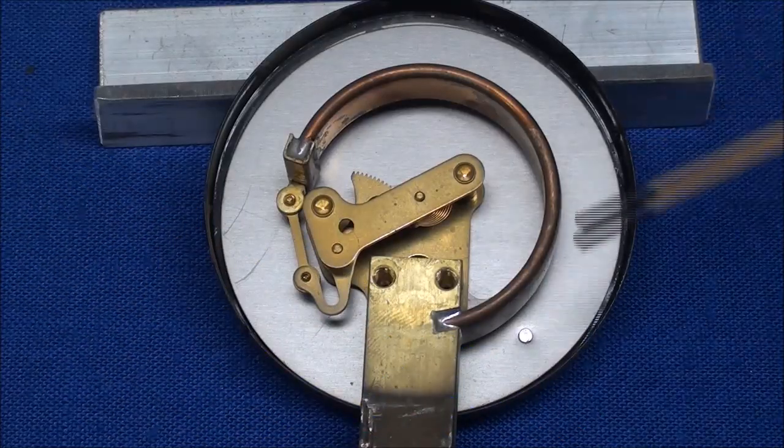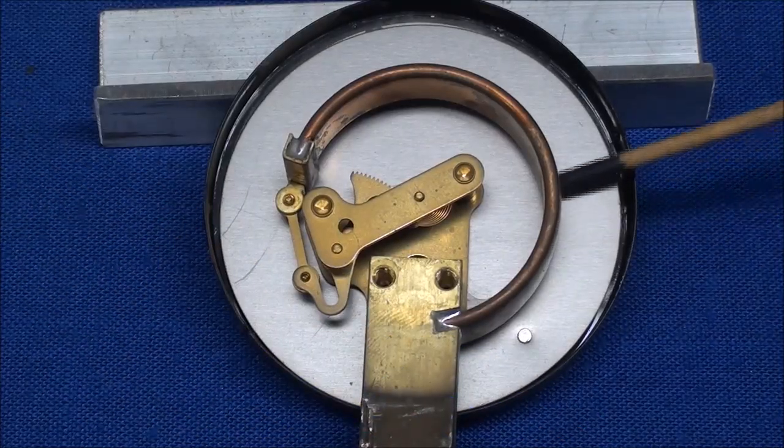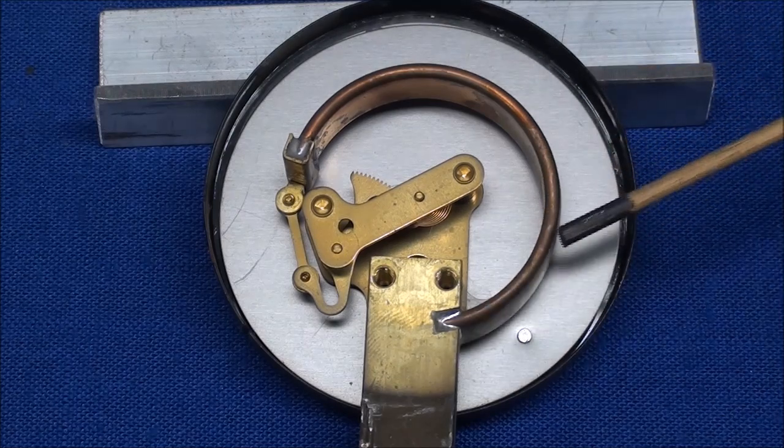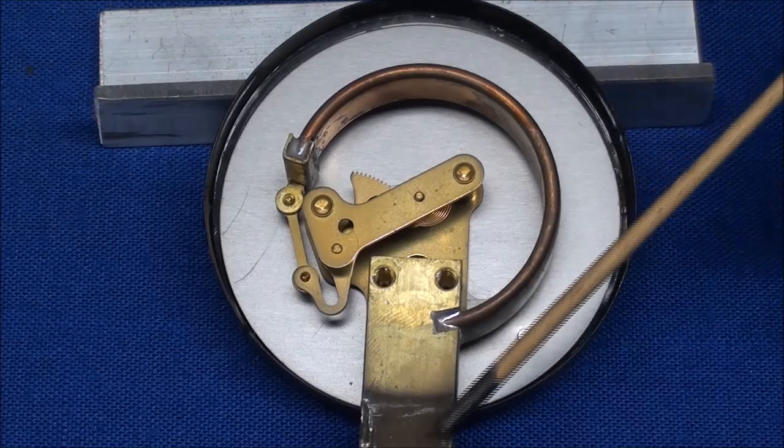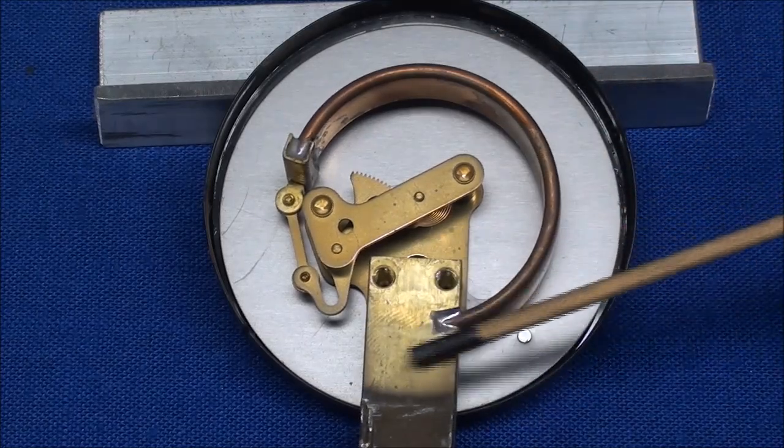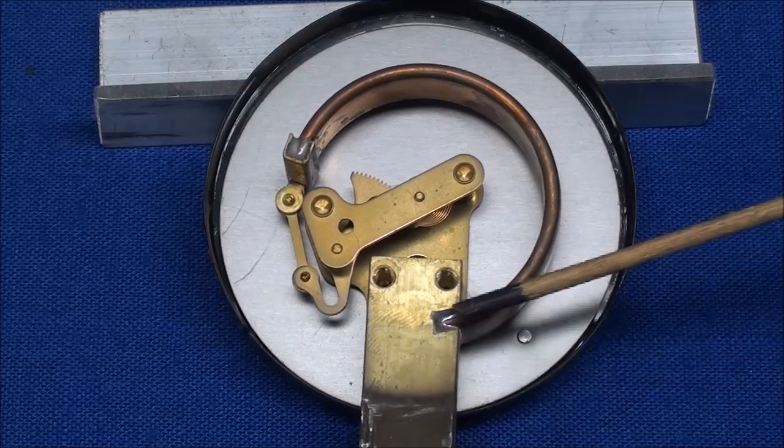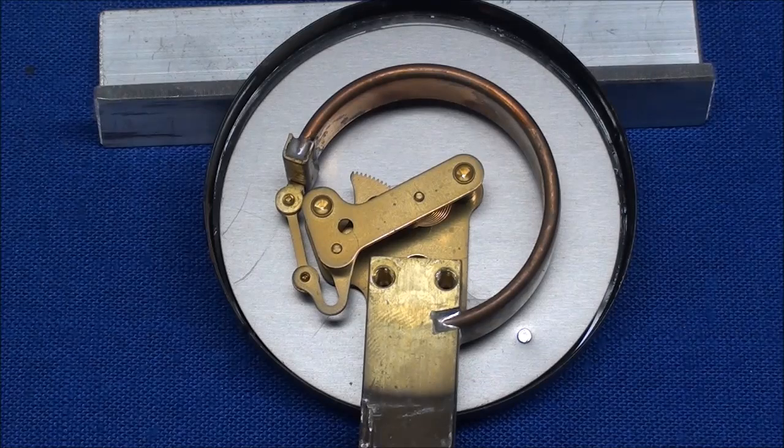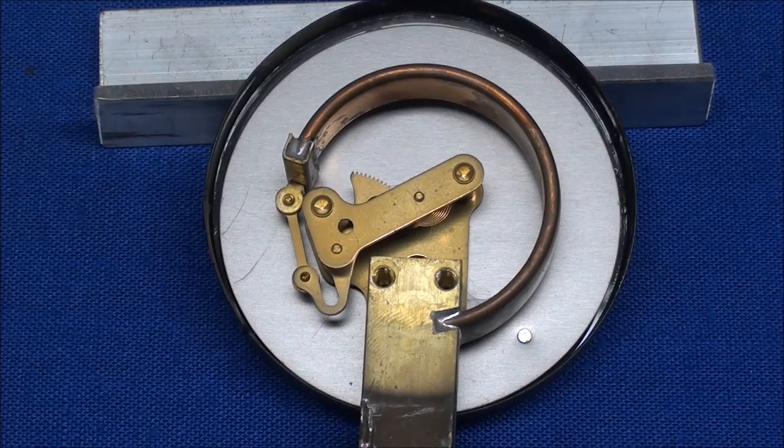The Bourdon tube is nothing more than a piece of copper tubing that has been flattened and then bent into a circular formation here. And it's soldered to the brass, the square brass part right here, just soldered, and then it's also soldered on the other end so that it is leak proof, in other words, air tight.